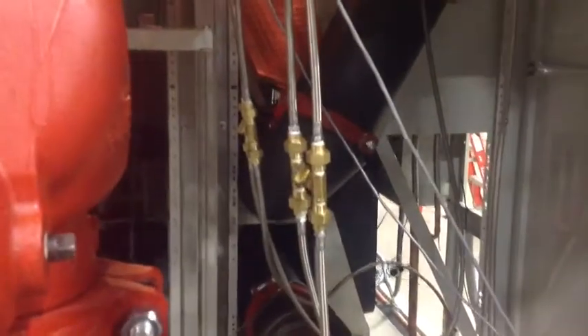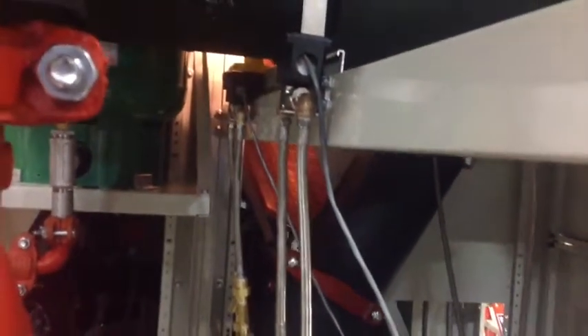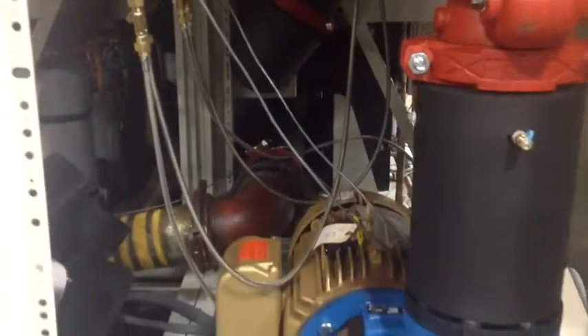In this first frame, at the brass connections, you can see 4 stainless steel braided gauge hoses. 2 of those tie into the pump discharge, and 2 of them tie into the leaving side of the chiller. This gives us 2 sets of differential pressure readings across the chiller: 2 into the chiller and 2 out of the chiller.